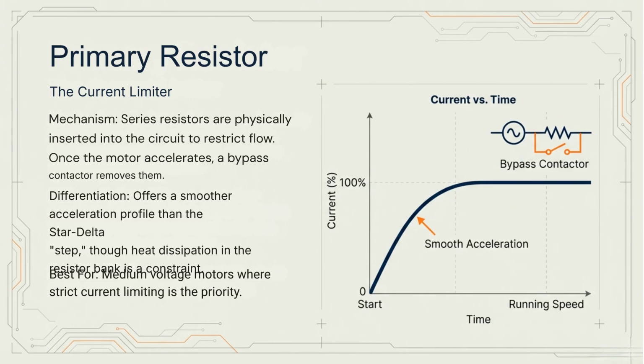Primary resistor starting uses series resistors inserted into the circuit to restrict current flow. Once the motor accelerates, a bypass contactor removes them.